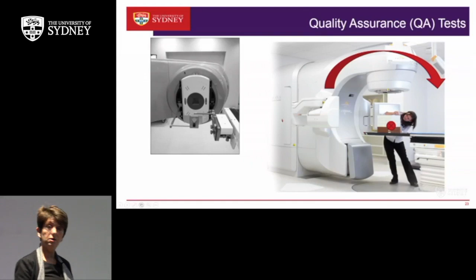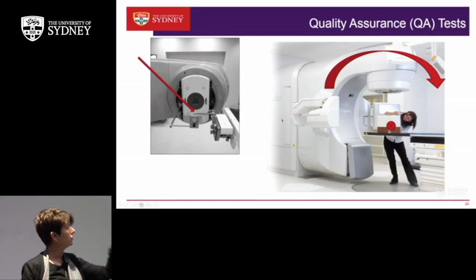So how do we check that this huge machine is focusing the radiation at a point in space which is no bigger than 1 millimetre? That's actually a very difficult thing to do. So this is a test that we do. So we have here a ball bearing which is placed at that isocenter, at that point in space that the gantry rotates.